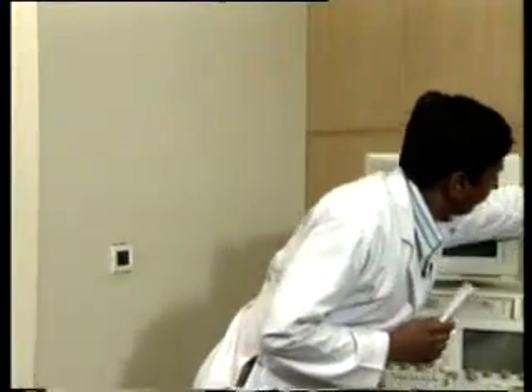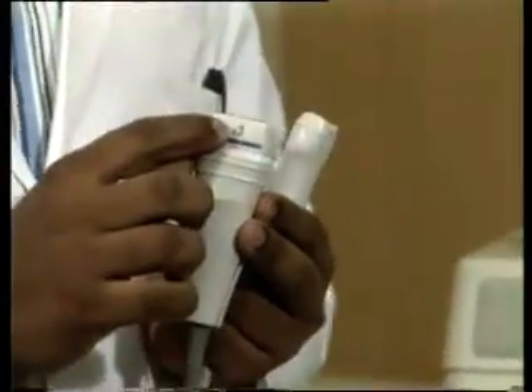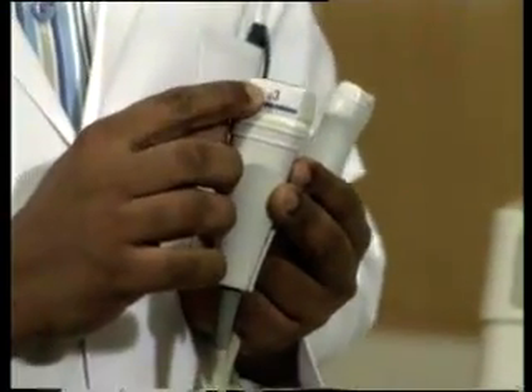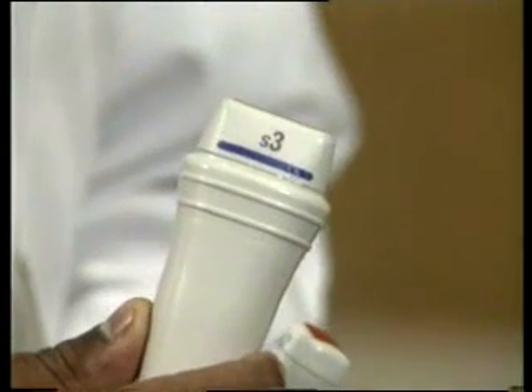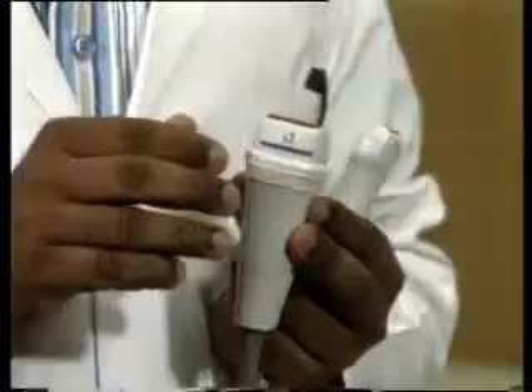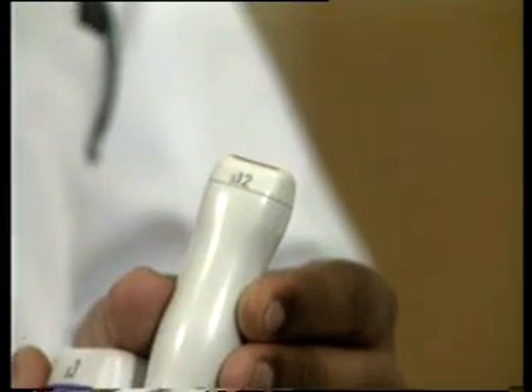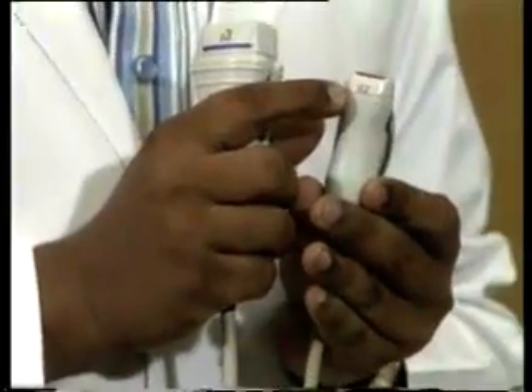Now there are different types of probes used for different purposes. The probes differ mainly in two aspects. One is the frequency that they emit, and second, the technology used for moving the ultrasound beam. Now these are various probes. These are two different probes. The number written here denotes the frequency that it emits. For example, in this case it is S3, so it emits ultrasound waves with a frequency of around 3 megahertz. Similarly, this probe has S12 written on it, which means it will emit ultrasound beams with a frequency of around 12 megahertz.